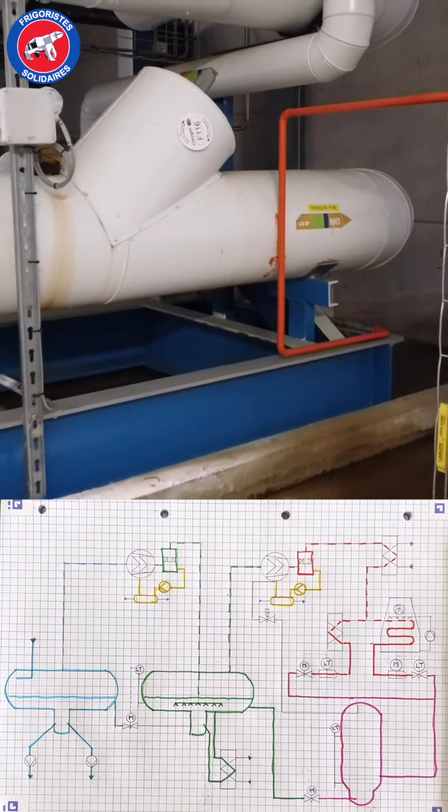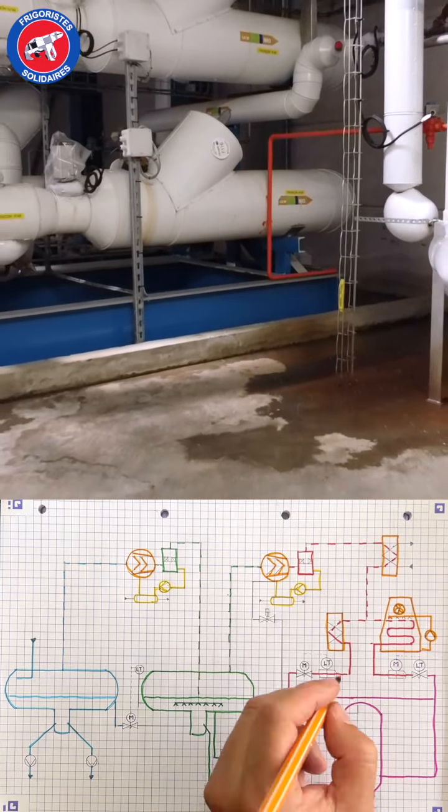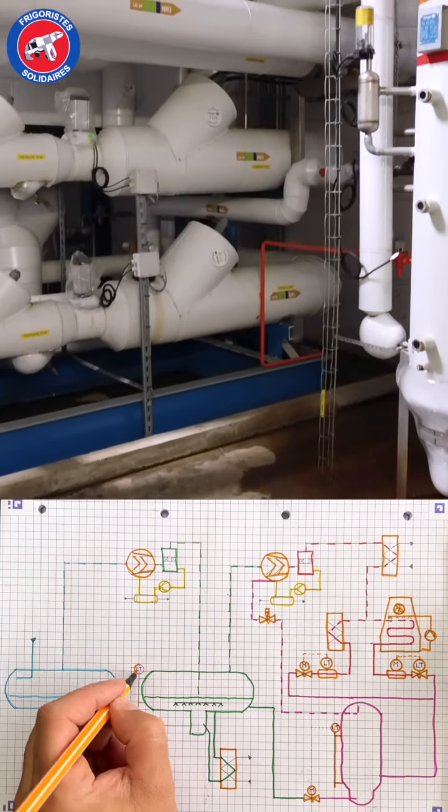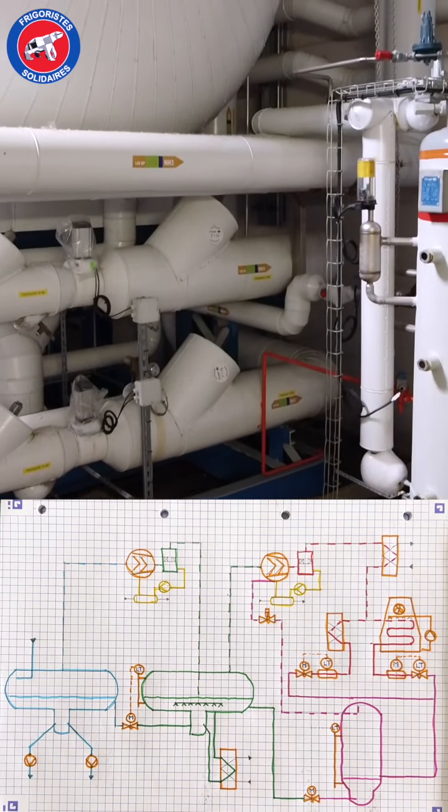The level of liquid in the medium pressure receiver is controlled by a level transmitter which drives the expansion valve feeding the low pressure part at minus 42 degrees C.